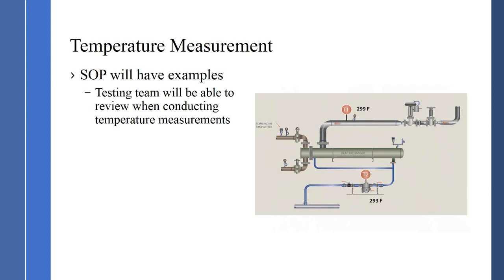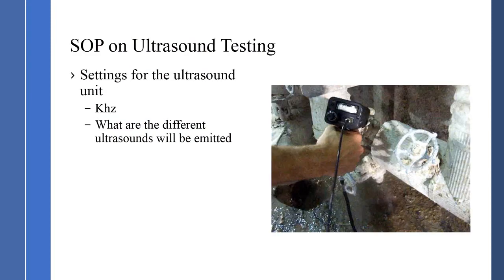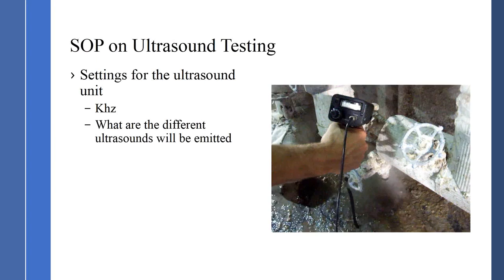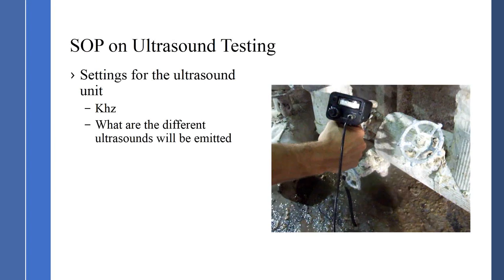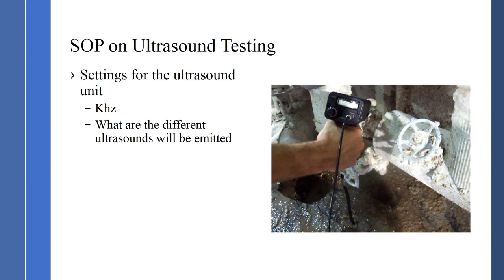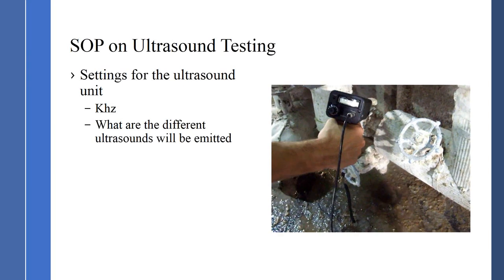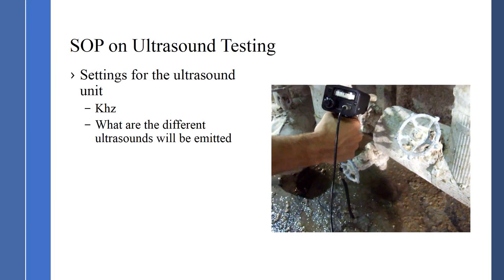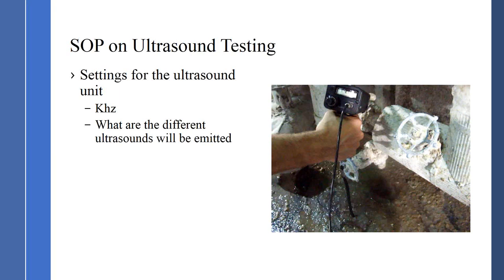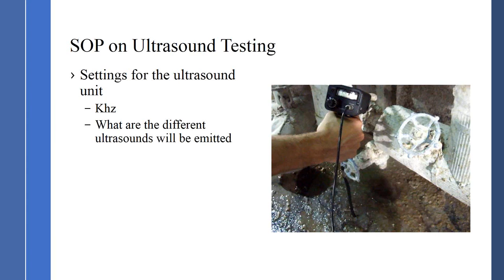The SOP also goes through the settings of the ultrasonic unit — what kilohertz setting to use, how to adjust the sensitivity of the ultrasonic units, the operation of the different types of steam traps, and the ultrasonic sounds emitted by each. This is very detailed because there are three major groups of steam traps: mechanical, thermodynamic, and thermostatic. We must ensure people understand the testing procedures for each of those three groups.